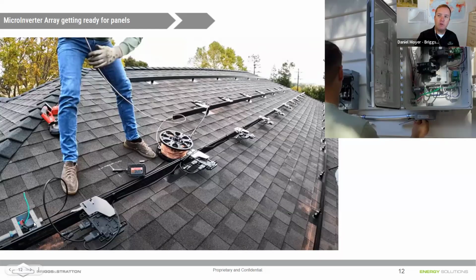And then we're coming down the roof, feeding it AC. We feed that AC into our IQ combiner box up here. This right there, I think, is a breaker just feeding the IQ Envoy that's inside there. And then we're feeding off back to our main electrical panel to a backfed breaker.